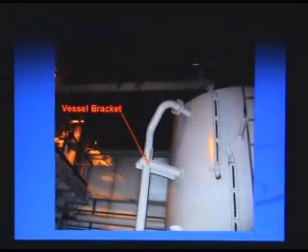And this is another kind of support, coming from the vessel, and it picks up the weight of this pipe. This support is strictly welded to the vessel. The advantage of this one is there's no thermal loads, even though it's a hard contact. Usually whenever you have a hard contact support with the pipe, you're going to have the load. There's no ifs and no buts. Whenever the pipe is sitting somewhere on a hard surface, it's going to create forces there.